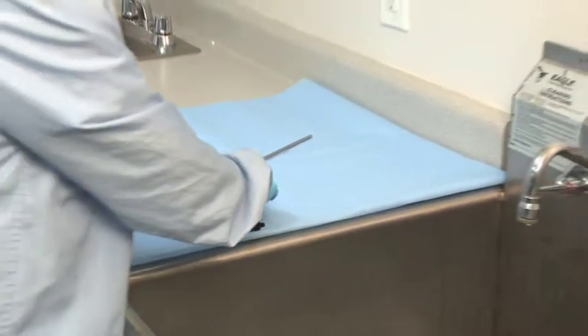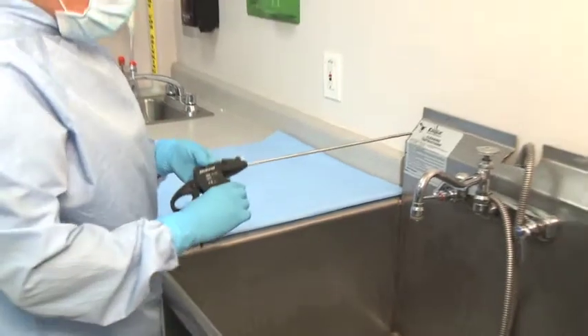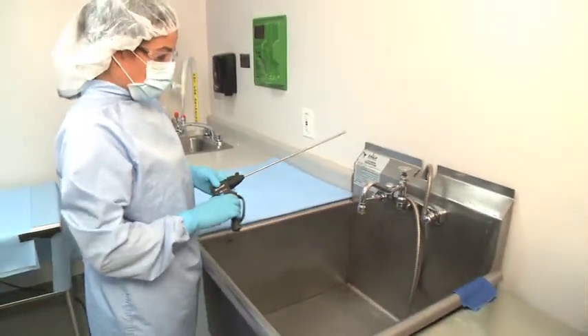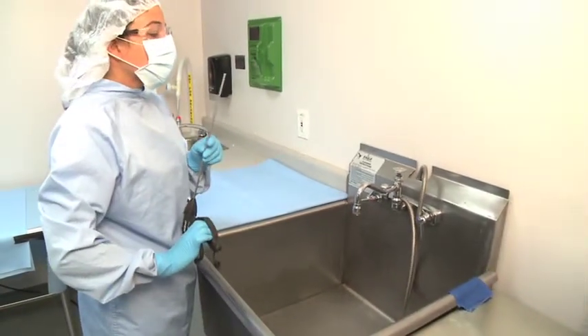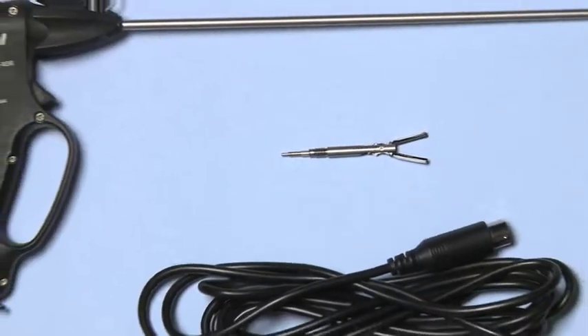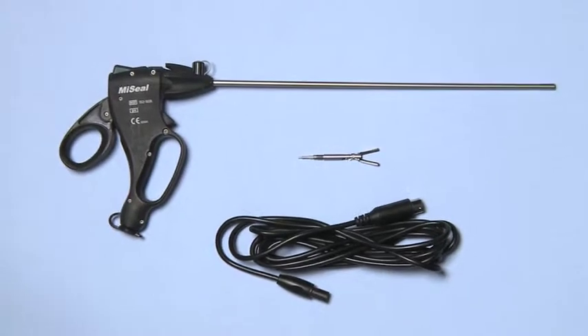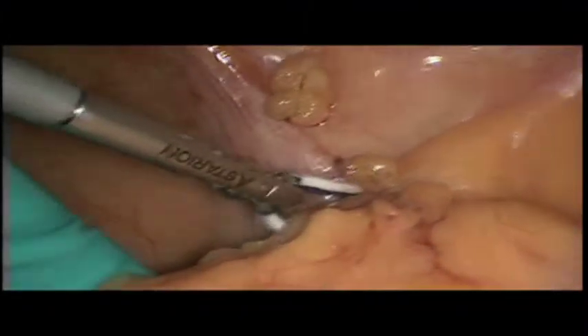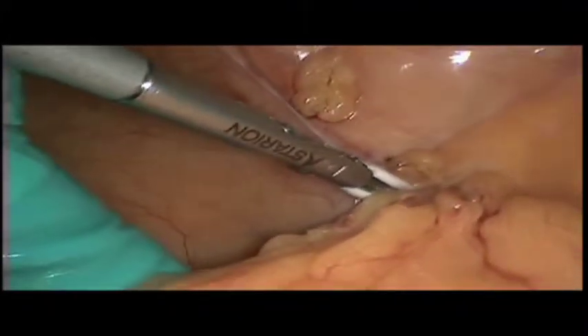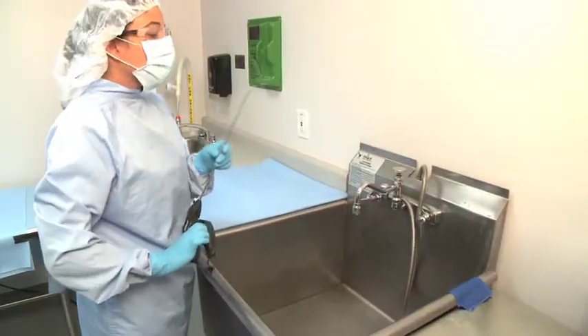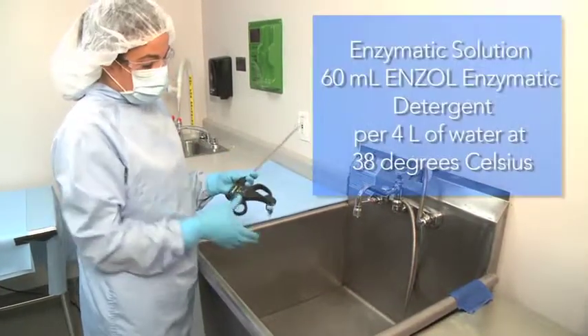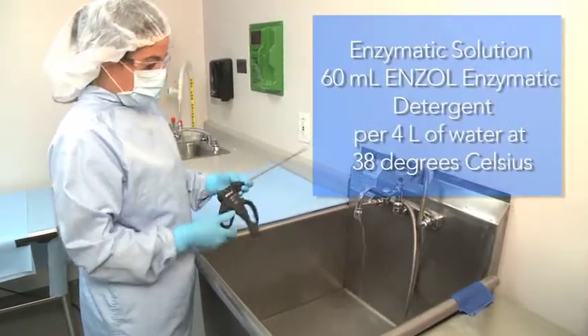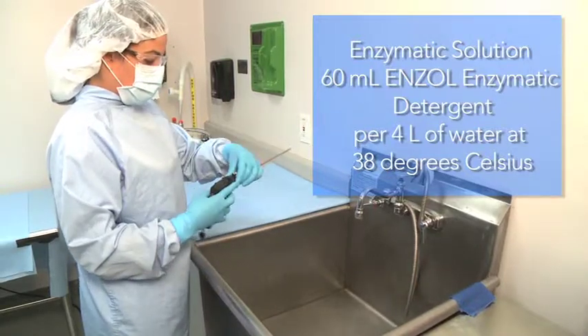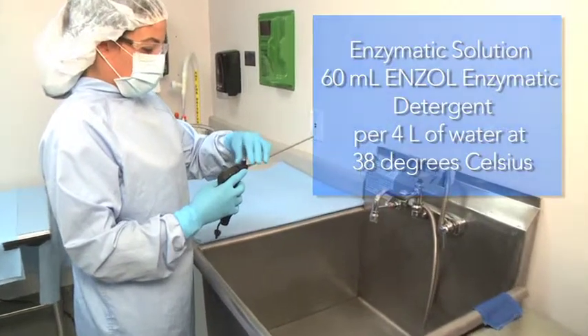The Miseal handpiece can be used multiple times when the cleaning and sterilization procedures detailed in the instructions for use are followed. The tip and cord are single-use only and should not be reprocessed. When the procedure is complete, the device should be cleaned using a prepared enzymatic solution containing 60 milliliters of ENZOL enzymatic detergent per 4 liters of water at 38 degrees Celsius.